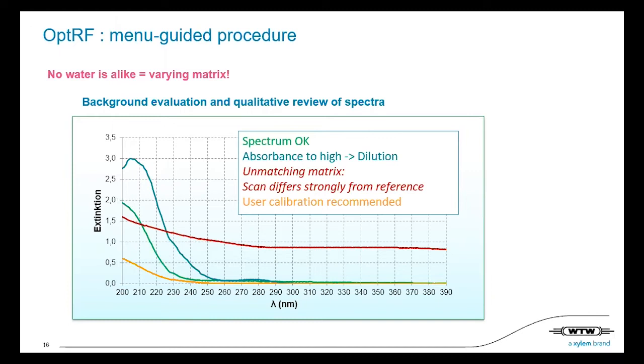Sometimes a user calibration is recommended because, as I said, we compare a real sample spectra in the background, and you know from IQ SensorNet that it can be good to make a user calibration to offset or correct the calibration curve. And then there are definitely water matrices which cannot be measured.